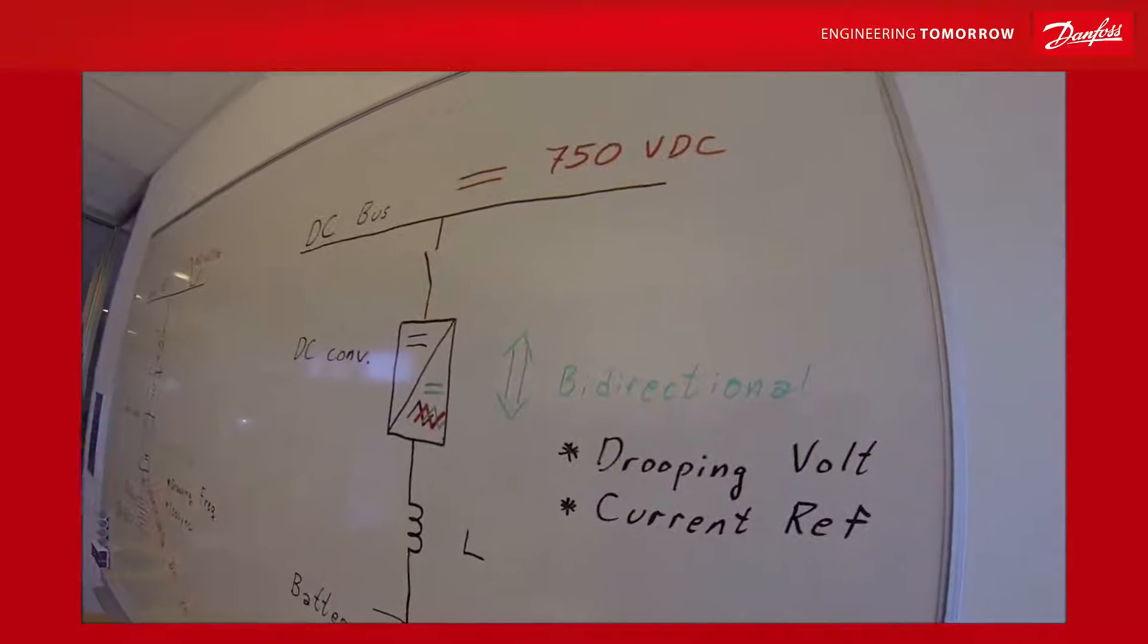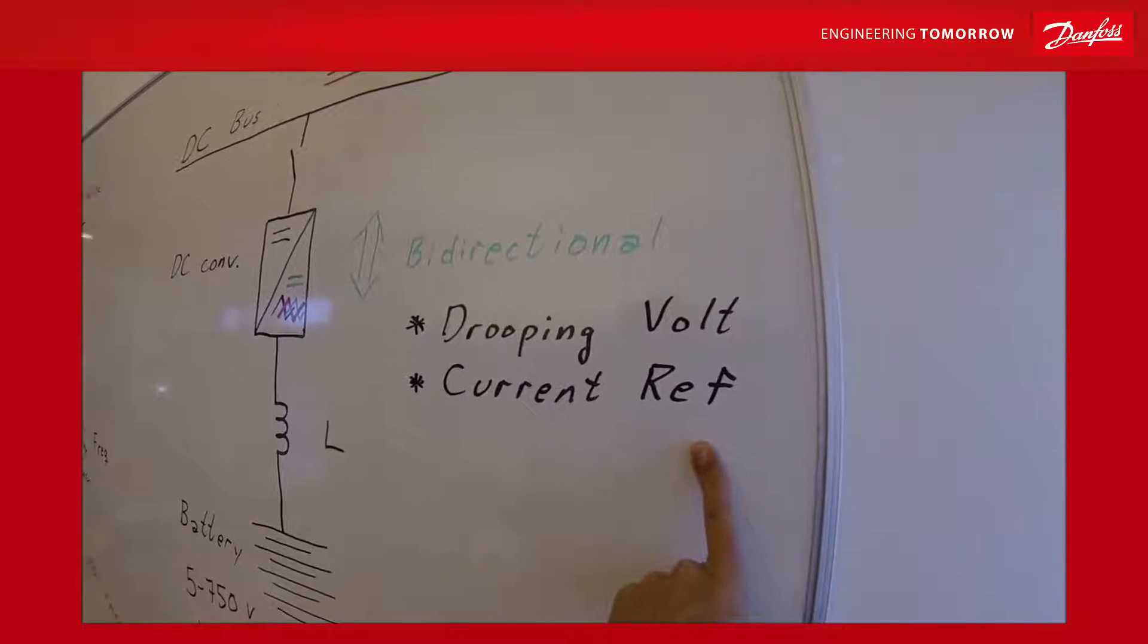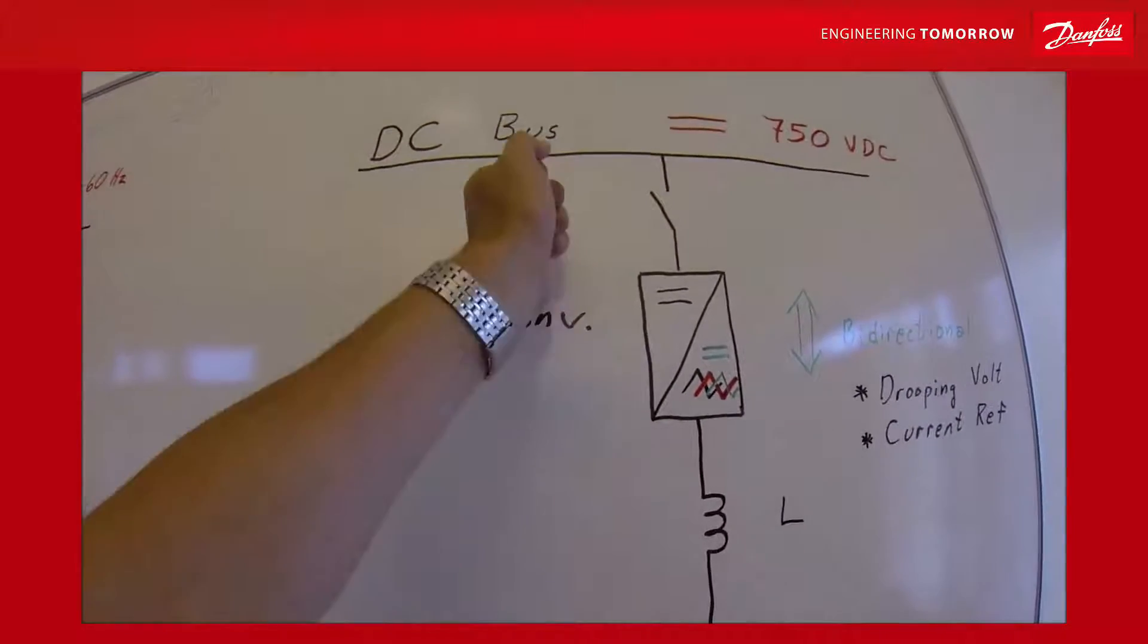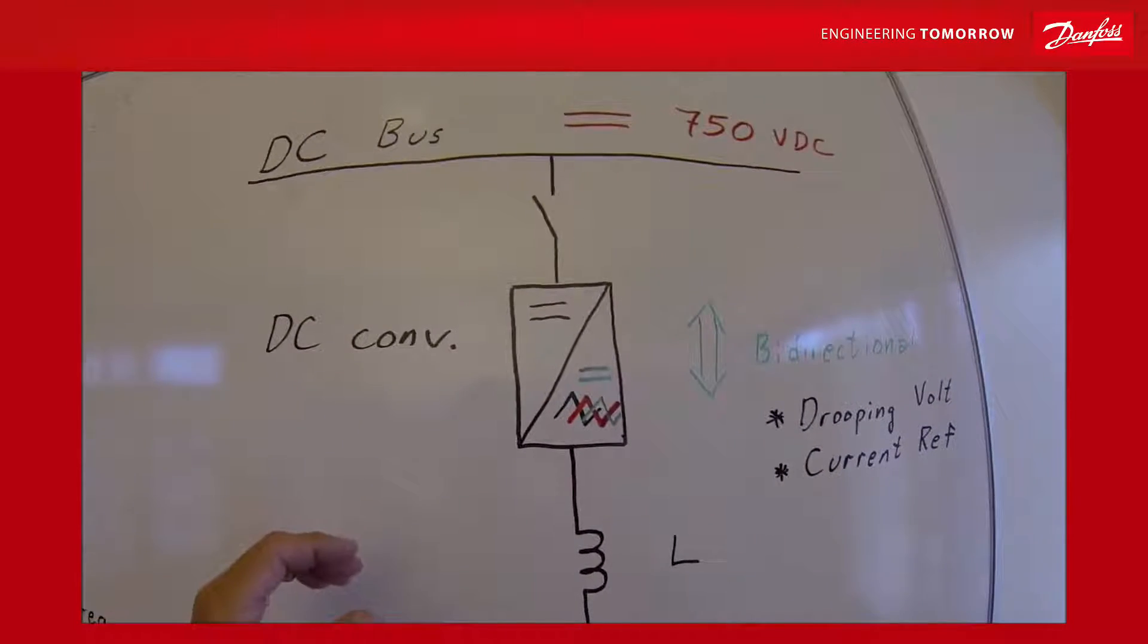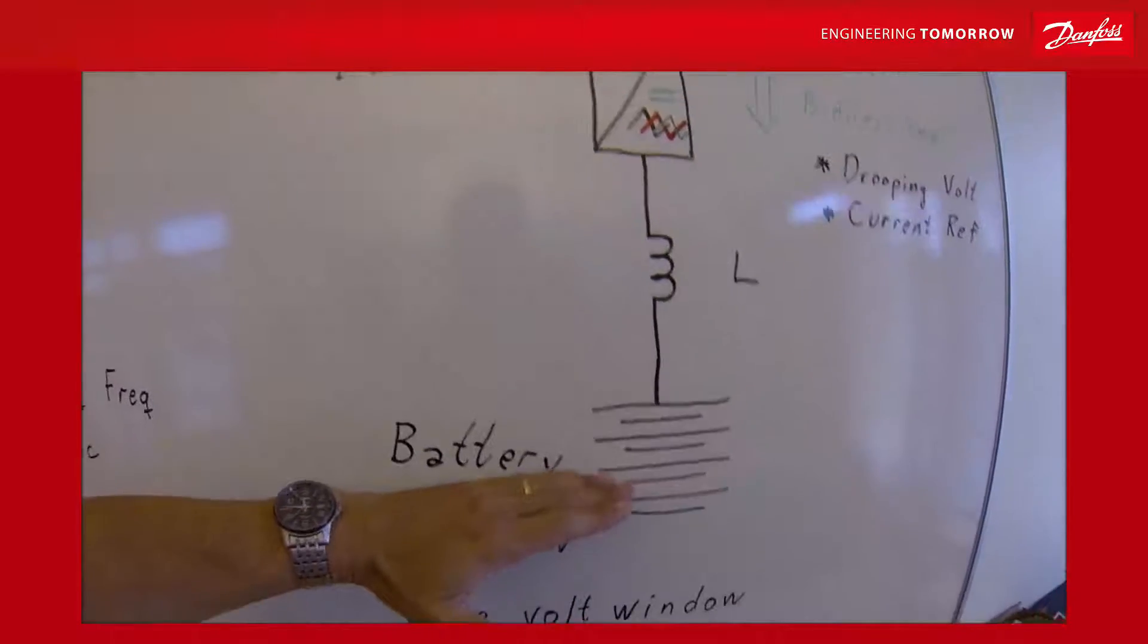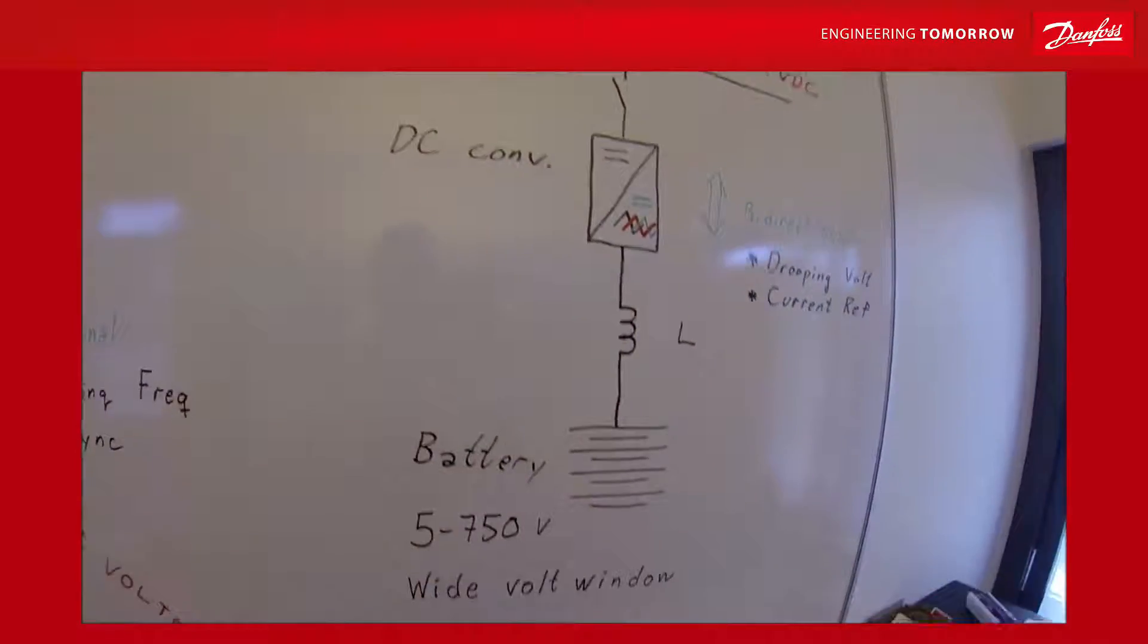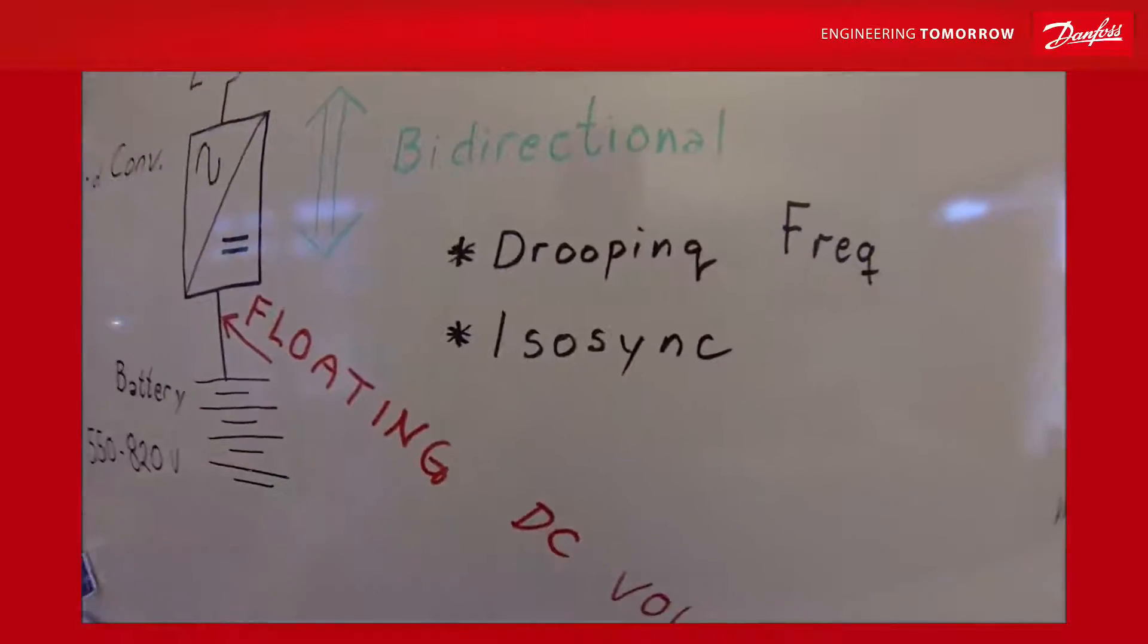Current reference is another way of controlling the DC DC converter. That is basically how like a power handle you control it from the PLC power management system, battery management system, and the operator decides how many amperes and which direction it should be. Should you give amperes to the bus or should you charge the batteries with a current coming from the DC bus to the battery? So in current reference mode it looks very similar to the grid converter in iso-synchronous mode.